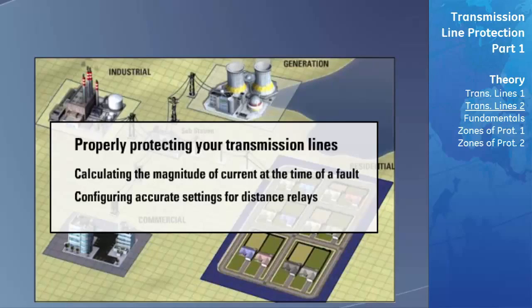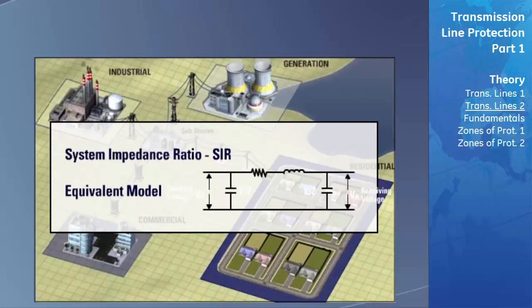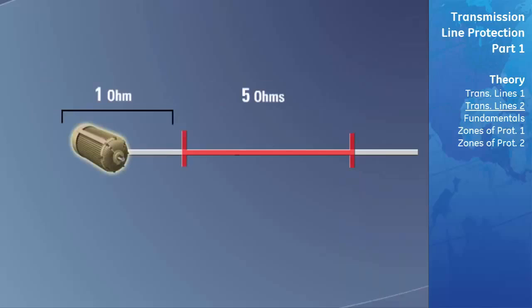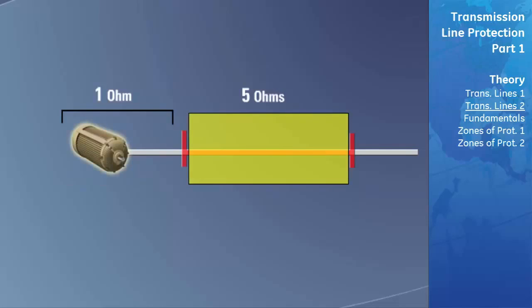In order to properly protect the line, the protection engineer must first calculate the system impedance ratio and develop an equivalent electrical model of the transmission line. The system impedance ratio takes the source impedance of the system behind the transmission line and divides it by the line impedance that is being protected.